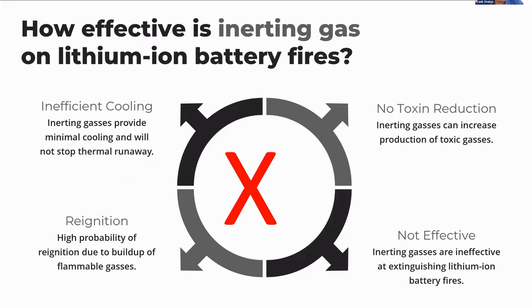The inert gas on lithium-ion battery fires. These gases as extinguishing agents were used a lot in places like data centers, where you're dealing with wiring and switching, and they are not very efficient at cooling. They will not stop thermal runaway. There's a very high probability we'll still have reignition because they can't cool sufficiently. There is no toxin reduction that they provide, and they're ineffective at extinguishing these fires. Basically, it's removing the oxygen out of those atmospheres, those enclosures.